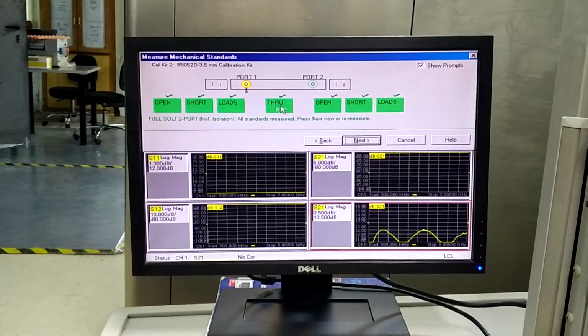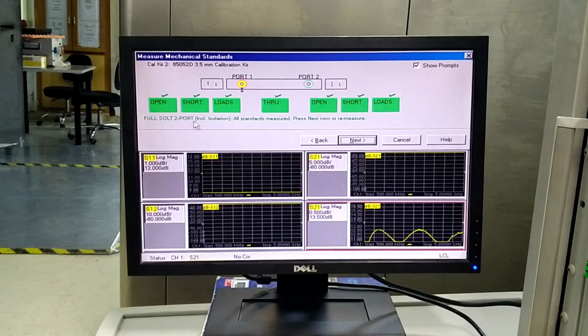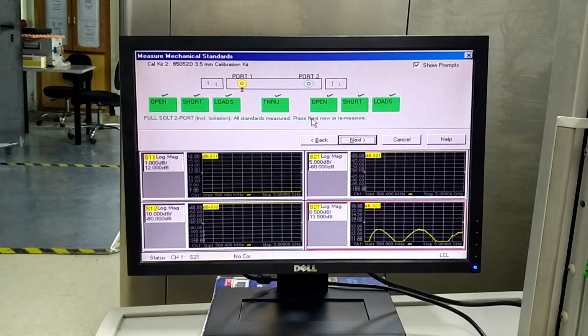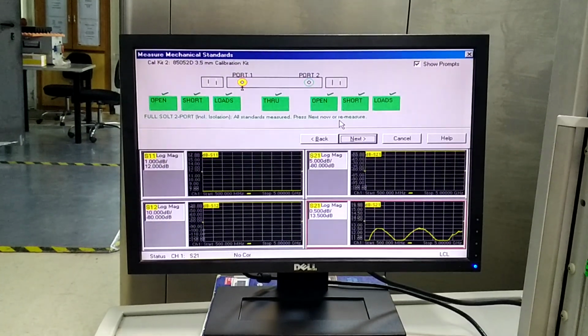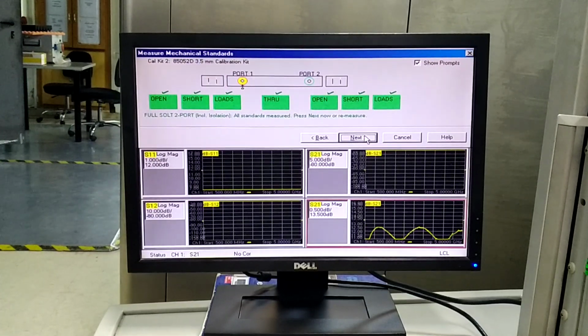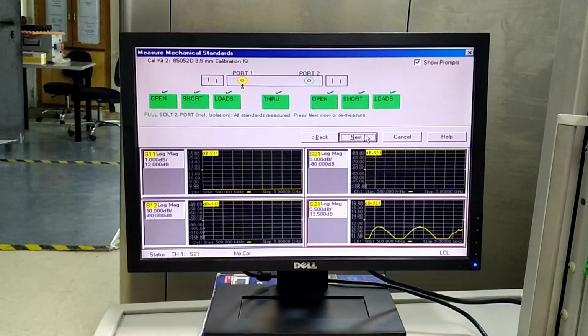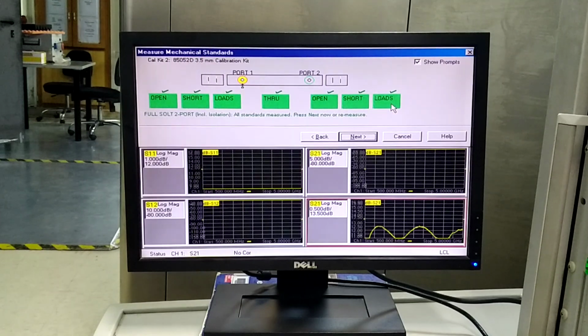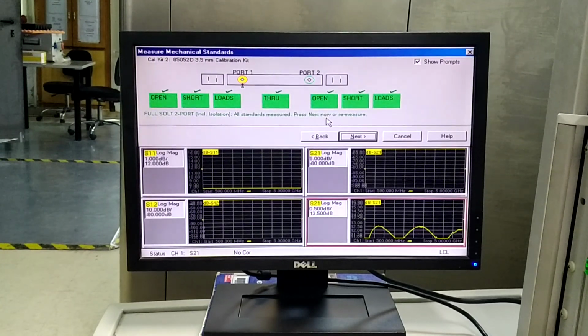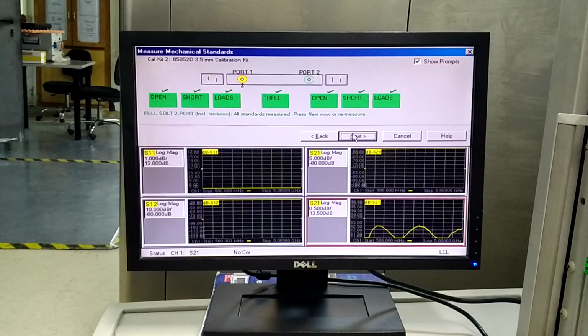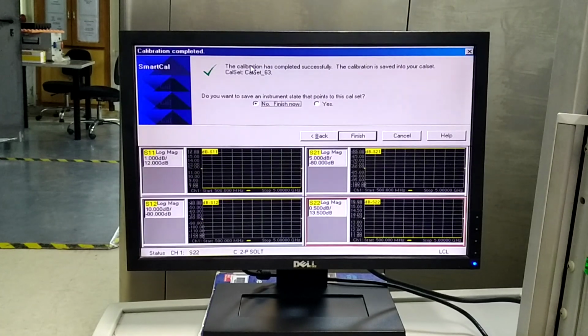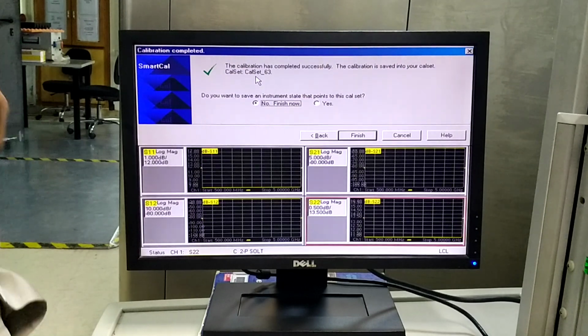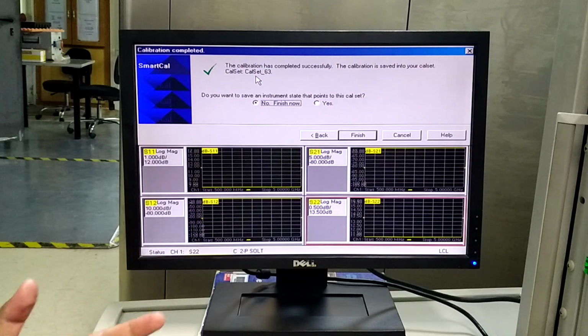I press OK. So now all the standards say full two port calibration including isolation, all the standards measured. Press the next button now if you would like to proceed with the end of calibration, or if you would like to remeasure, you can press the remeasure option as well. So I just press the next button now. It says calibration has been successfully completed. The calibration is saved into your calset. So it saved the calibration. This is the important thing that I would like to highlight, that typically a calibration expires after 24 hours because of drift error, as I mentioned in the class.